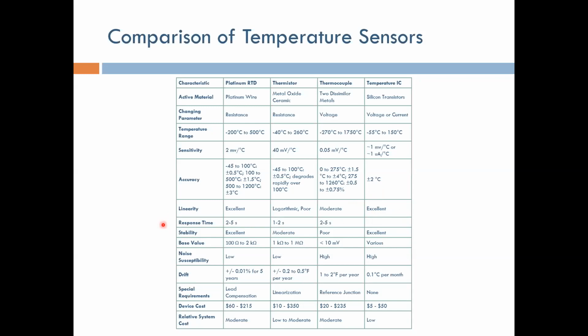Remember the response time—the time required for the resistance to change corresponding to a change in temperature, measured between 10% and 90% of the response. For RTDs, it's between 2 and 5 seconds, very similar to the thermocouple. For the thermistor, it's between 1 and 2 seconds. Again, you might find things much faster now. The faster the response time, the better the sensor, because it can follow quick changes in temperature very well.